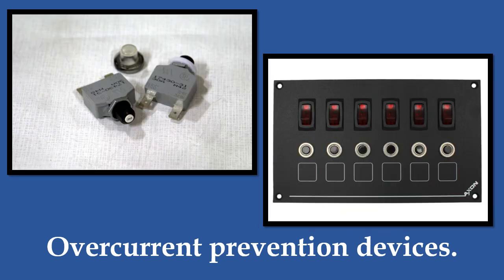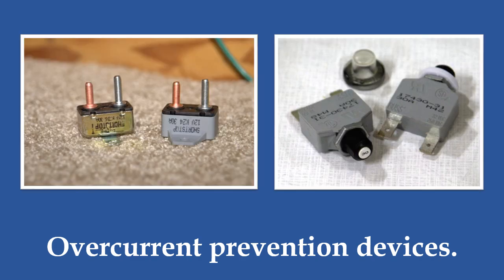Another type of breaker available is the push-button mini breaker. These are also utilized in the RV industry and are installed in a variety of breaker panel configurations. Many are designed to display an indicator light for the circuit that has been tripped. Blade-type fuses, automotive circuit breakers, and push-button mini breakers all must be marked with their maximum ampacity rating. These markings are required and necessary to assure that when conductors from the 12-volt system are attached, the wire size matches the overcurrent protection.